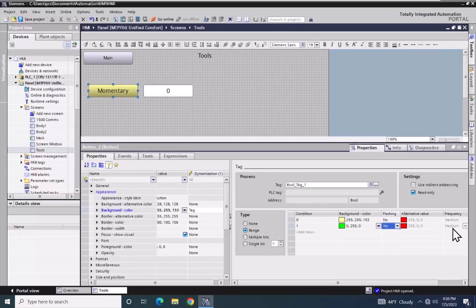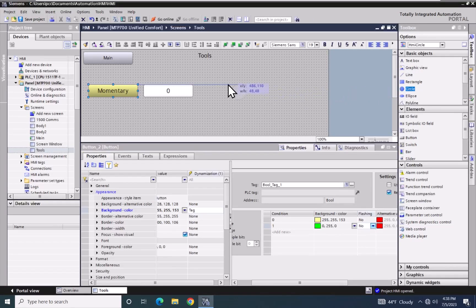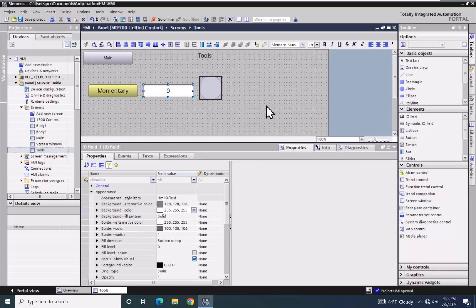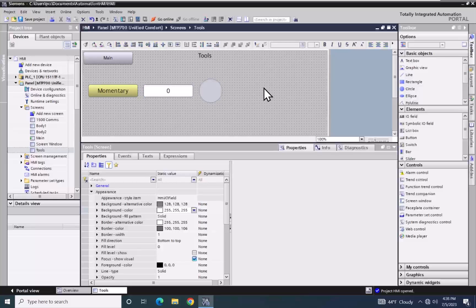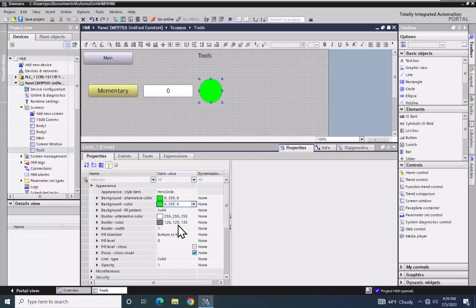You also have a flash frequency that you can set for how fast the flash rate is going to be for switching between the two colors. Next I am going to take a circle object and put it out on the screen and make it a little bit bigger, then center it. I'll select my IO field and the circle by holding down the shift key and selecting the two objects, then pick align selected objects horizontally. I'm going to select this circle object and pick the background color — right now it's set to a gray color, so I'm going to change it to a green color.